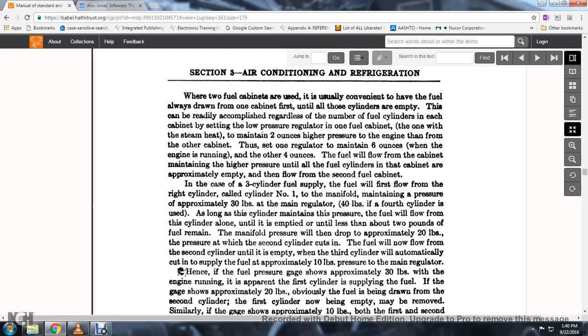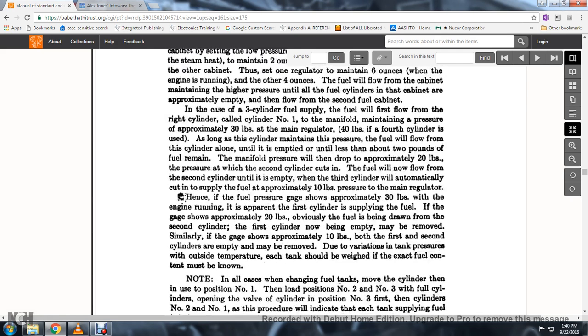In the case of a three-cylinder fuel supply, the fuel flows first from the cylinder connected to manifold number one, maintaining pressure of approximately 30 pounds at the main regulator, or 40 pounds for four-cylinder use. The cylinder maintains the pressure allowing the unit to empty until less than about two pounds of fuel remain. When pressure drops approximately 20 PSI, the second cylinder cuts in and fuel flows from it until empty; the third cylinder is automatically cut in when approximately 10 pounds pressure remains from the main regulator. If the fuel pressure gauge shows approximately 30 pounds with the engine running, the first cylinder is supplying fuel; at 20 pounds, fuel is drawn from the second cylinder; at 10 pounds, both first and second cylinders are empty and may be removed.